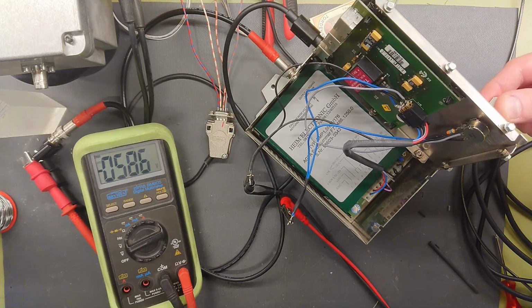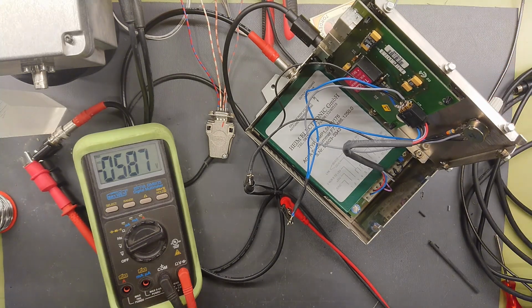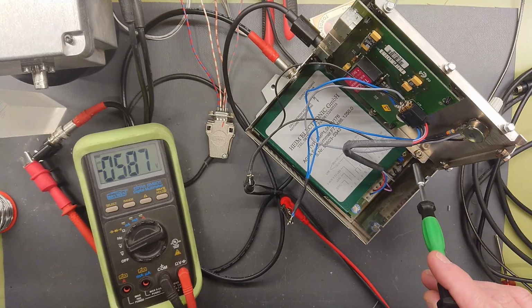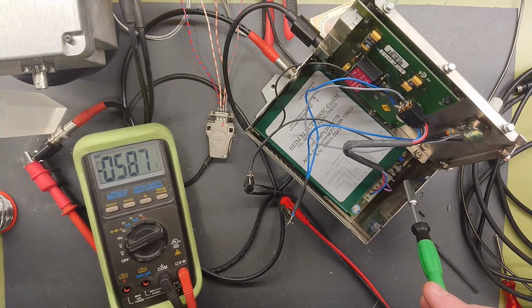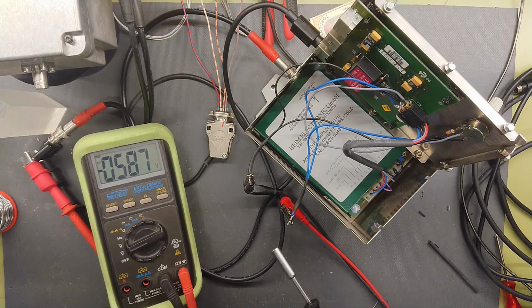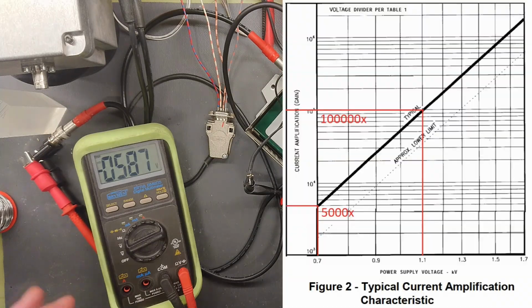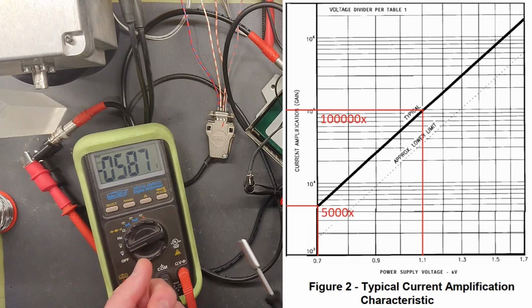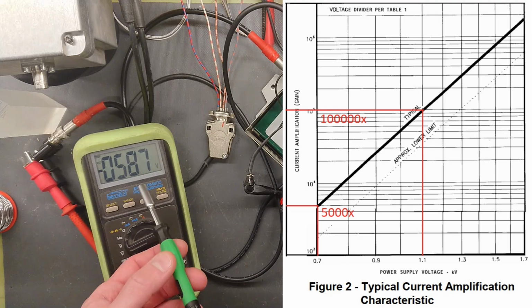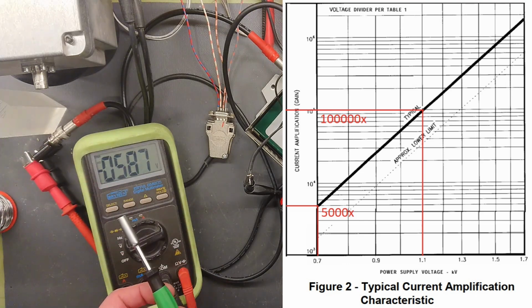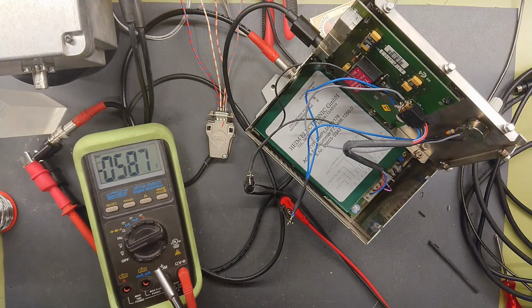Oops, but now there can the knob here. So I guess the high voltage adjustment potentiometer that we have down here at the power supply is adjusted way below the capability of 1.5 kilovolts, as I'm only at minus 600 right now. But that also makes sense that these PMT tubes used for image scanning are not driven that hard, so they usually use a lower voltage on the whole photon acceleration chain.